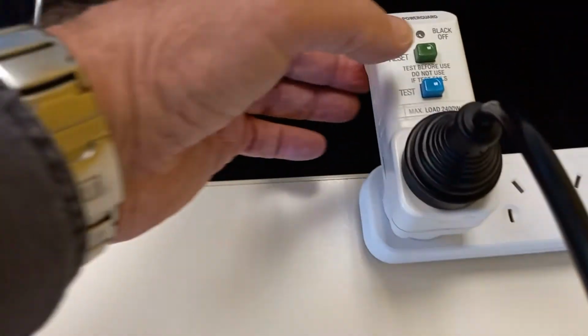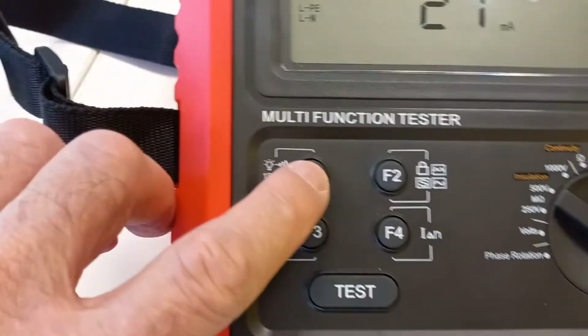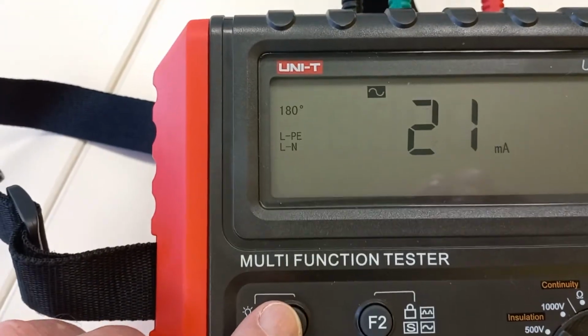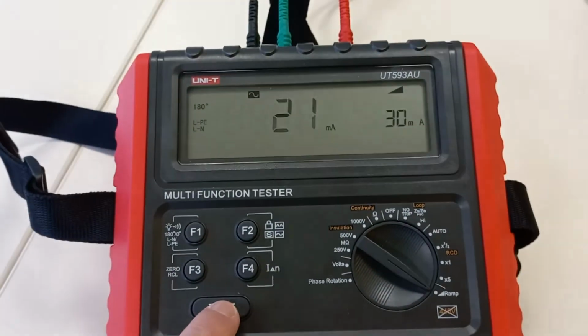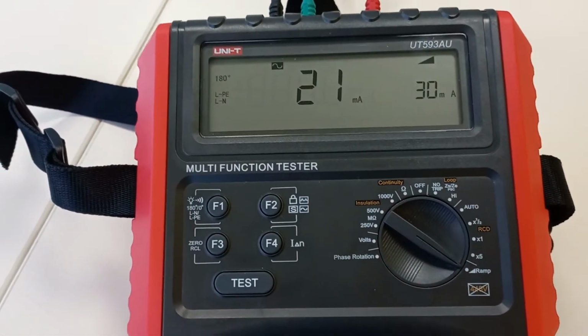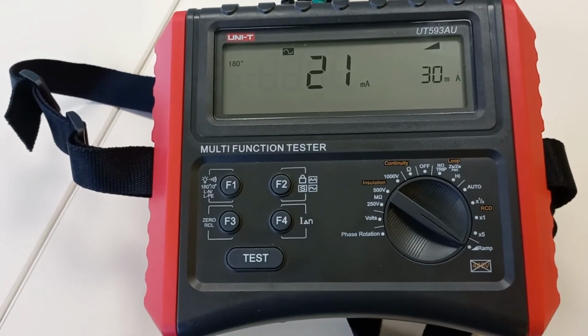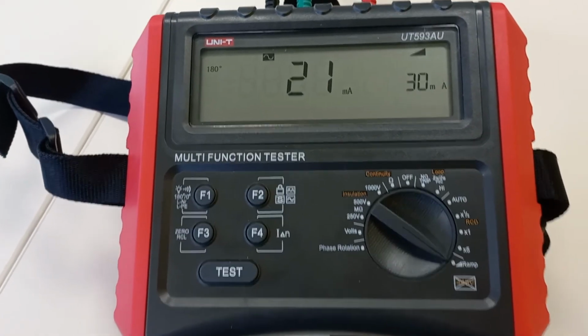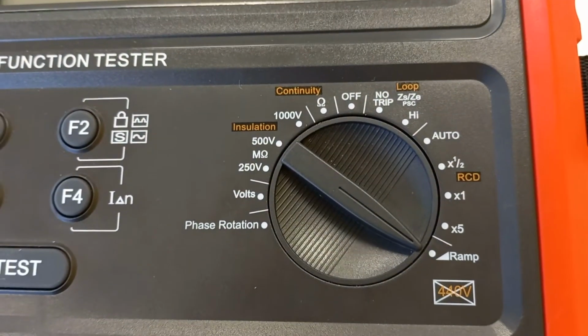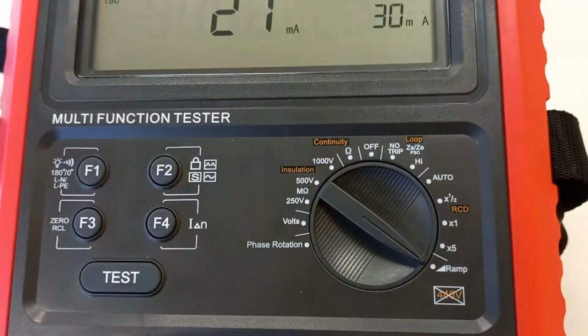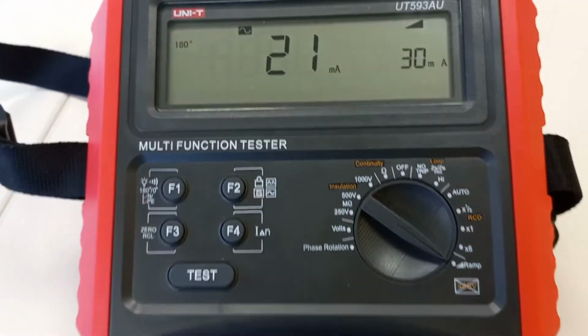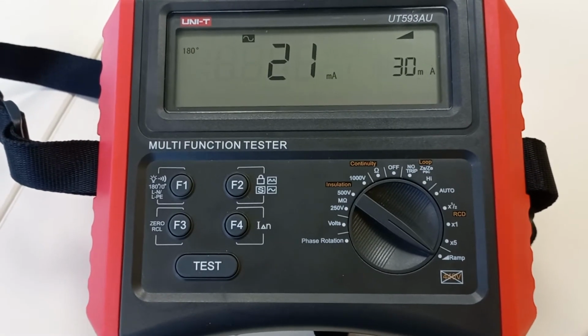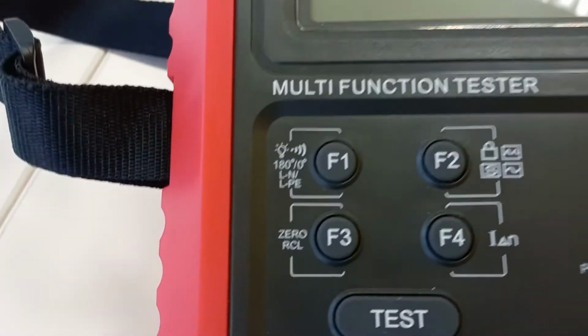Now I reset. Let's reset again. Now I move to 180 degrees. This is 180 degrees. Test again. This time it's tripped out at 21 milliamps. So that's using the ramp function for the actual tripping current, and I find the auto function is the nicest way to do the tripping times and then play them back using the recall.